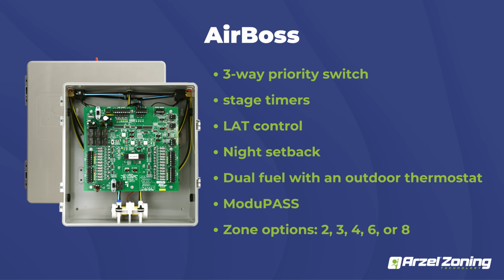The AirBoss is also going to ship with your LAT protection. So it has an LAT sensor, which will go up into your leaving air temperature, into your plenum. That's going to give you all your lockouts as far as overcooling or overheat. So if that equipment starts to get too cold or too hot, it's going to start staging your equipment back or shutting it off and running the fan until normal temperatures come back on the panel. And that ships with every AirBoss, so it's not an added thing.